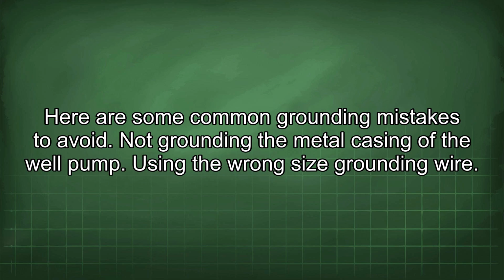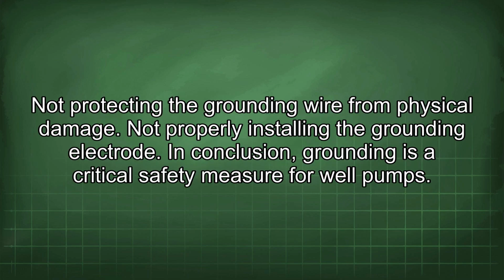Here are some common grounding mistakes to avoid. Not grounding the metal casing of the well pump. Using the wrong size grounding wire. Not protecting the grounding wire from physical damage. Not properly installing the grounding electrode.